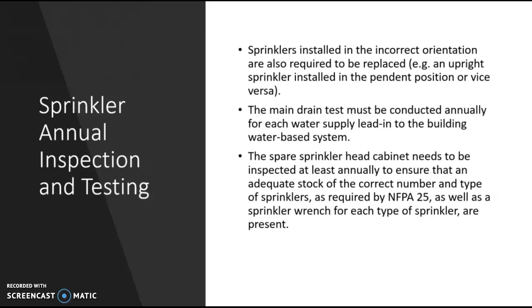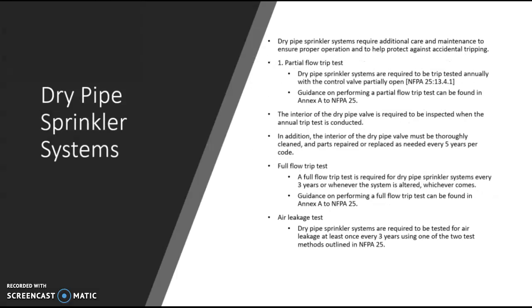The spare sprinkler head cabinet needs to be inspected at least annually to make sure there's enough of the correct types of sprinklers, and we have to make sure, once again, that there is a wrench. The dry pipe sprinkler systems require additional care and maintenance to ensure that they work correctly. Once again, we're all worried about the accidental tripping, of course, with the dry pipe system, so it doesn't fill up with water. One is the partial flow trip test.